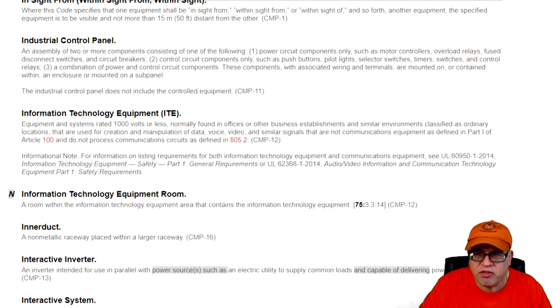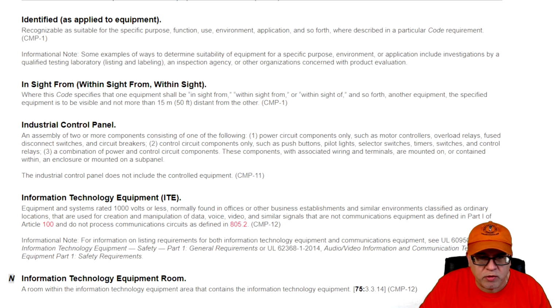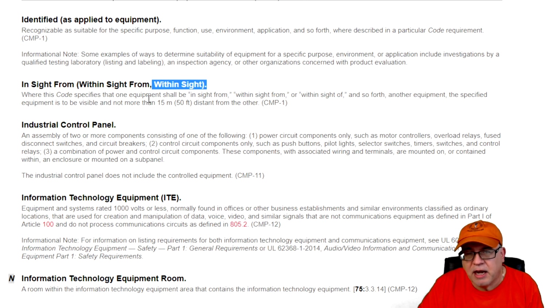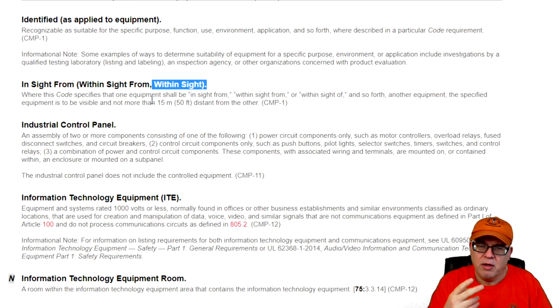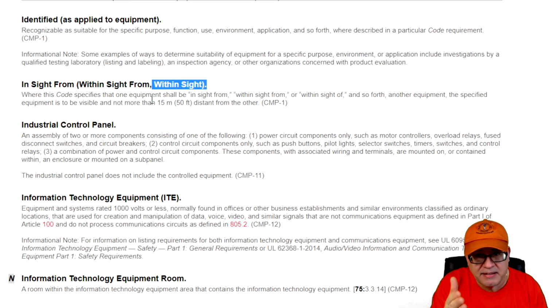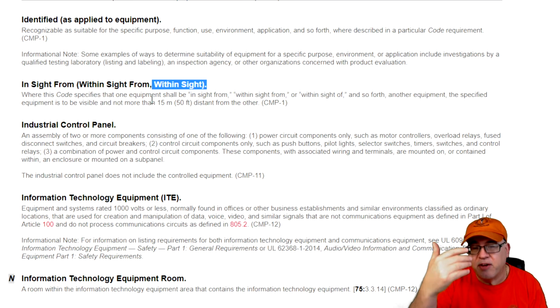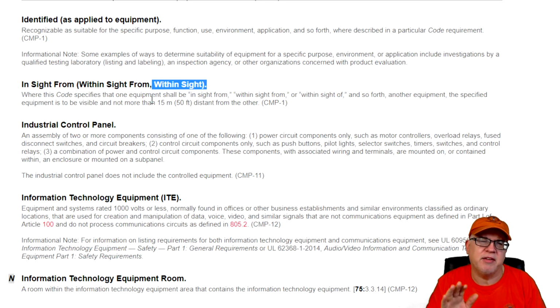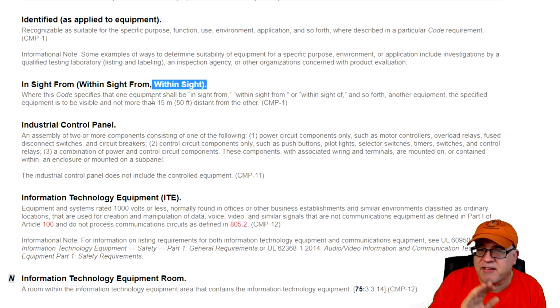Here's one that people should know, just in the general course of understanding: in sight from, which in the code might be referred to as within sight from. Just remember that there are two components to this. One, it literally has to be within sight. You've got to see it. And two, it cannot be more than 50 feet from you. So if it was 55 feet, it is theoretically still within sight, unless you can't see like me, but it doesn't qualify when it comes to the NEC as being considered in sight from, or within sight from, or within sight, okay?